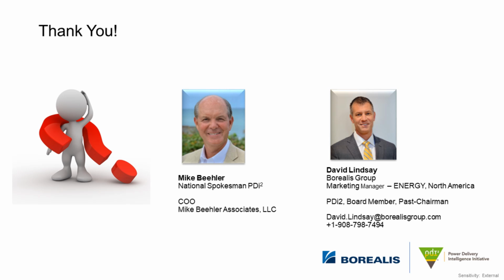Okay. I'm going to ask another question from the same utility out west. Thanks for the questions, by the way. Are the losses higher for copolymer WTR than standard cross-linked polyethylene? I assume we're talking about electrical losses here. I'll make that assumption. And the answer is no. They're very, very similar. I don't think you would ever notice a difference, and they are much lower than EPR. Okay. Ethylene propylene rubber, yeah.